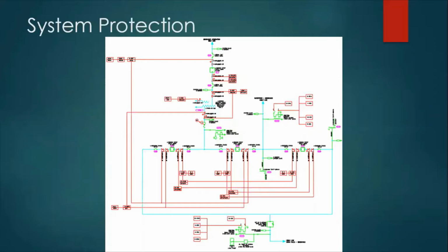The first deliverable of the spring semester's control design was the one line with relaying, as shown here. This schematic is the base for every following schematic, as it outlines each device with its ANSI classification based on how the relays would be configured. This universally communicates what function our substation is capable of and the level of redundant protection throughout the substation and on the Watertown and Sioux Falls line exits.